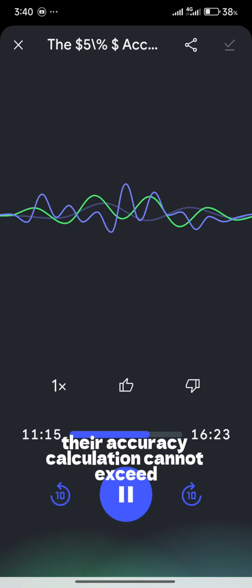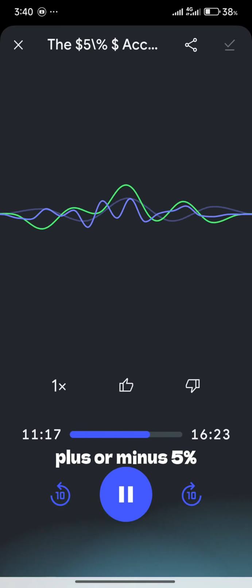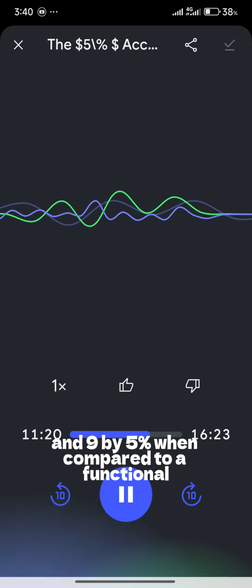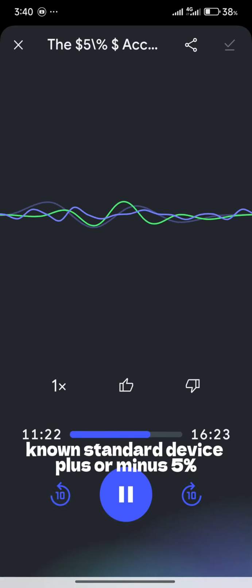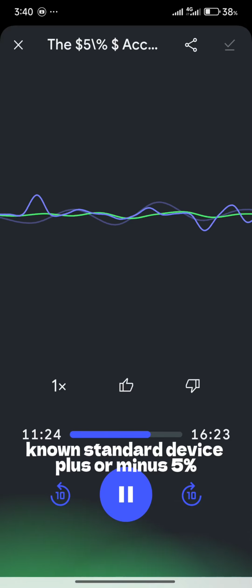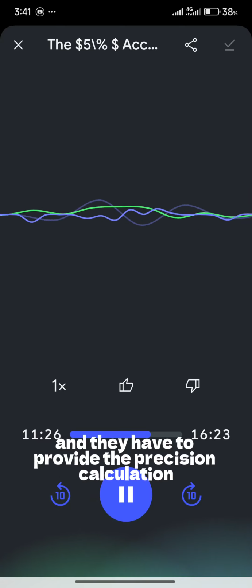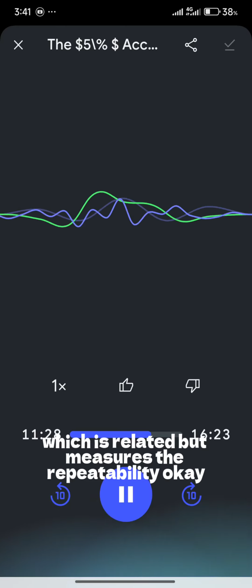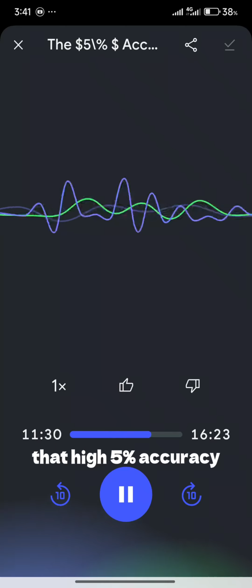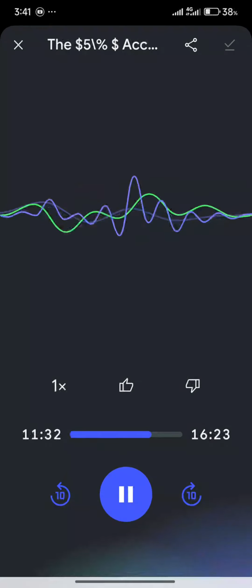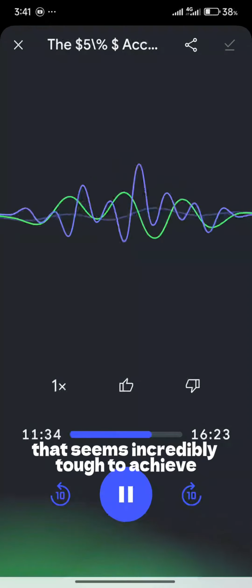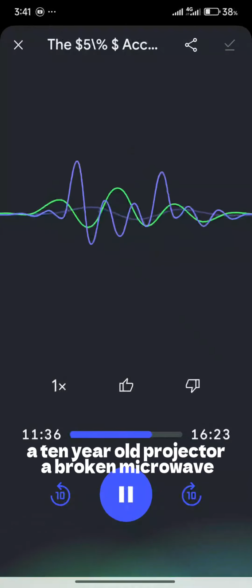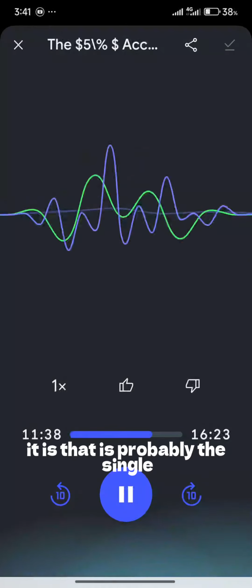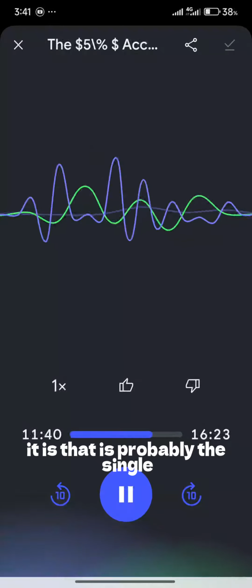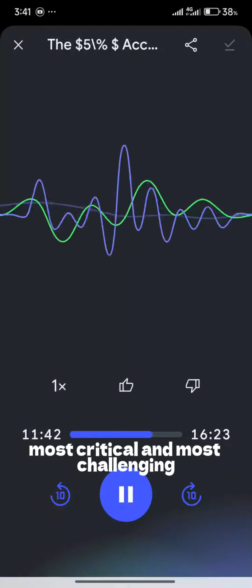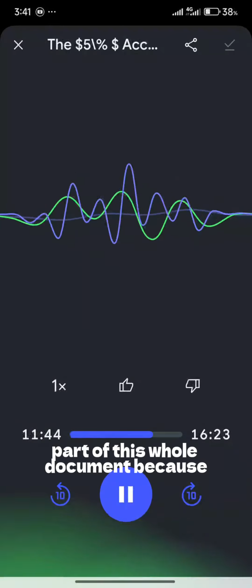That's the one. Their accuracy calculation cannot exceed plus or minus 5% when compared to a functional known standard device. Plus or minus 5%. And they have to provide the precision calculation as well, which is related but measures the repeatability. Okay, that high 5% accuracy seems incredibly tough to achieve with parts pulled from a 10-year-old projector or a broken microwave. It is. That is probably the single most critical and most challenging part of this whole document.